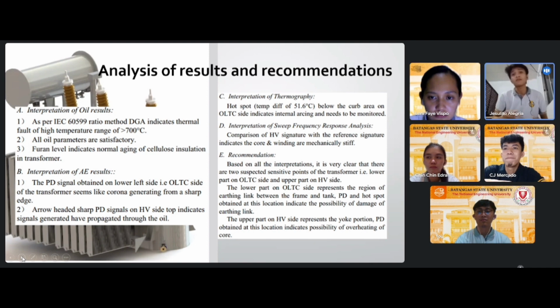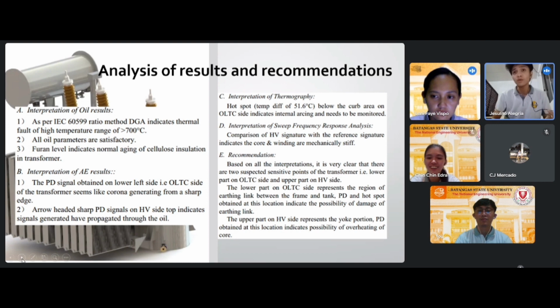Third interpretation is from the thermography. The hotspot temperature difference of up to 51.6 degrees Celsius below the curved area on the OLTC side indicates an internal arc and needs to be monitored. Fourth interpretation is from the sweep frequency response analysis. The comparison of the high voltage signature with the reference signature indicates the core and winding are mechanically stiff.